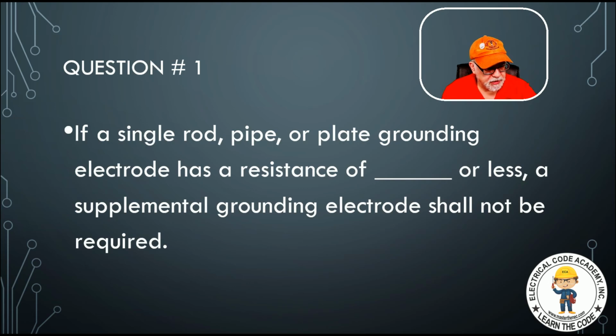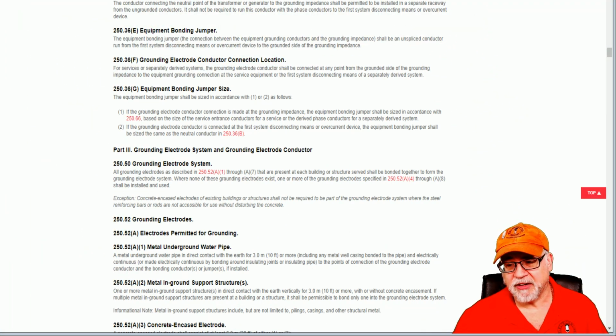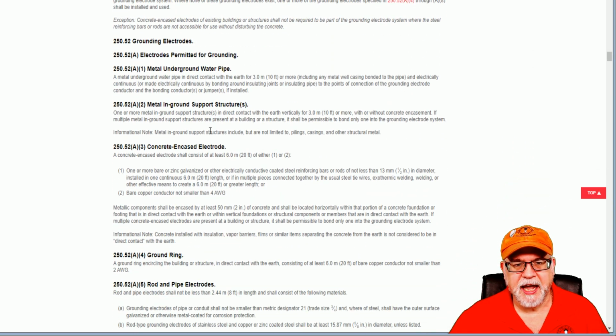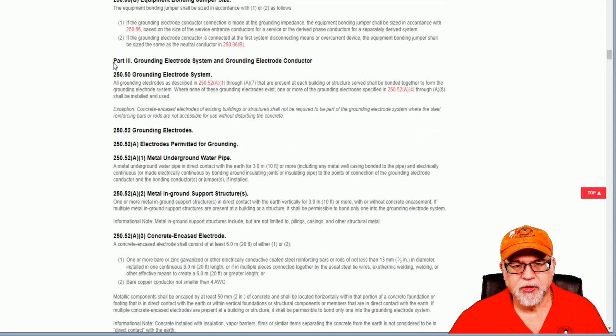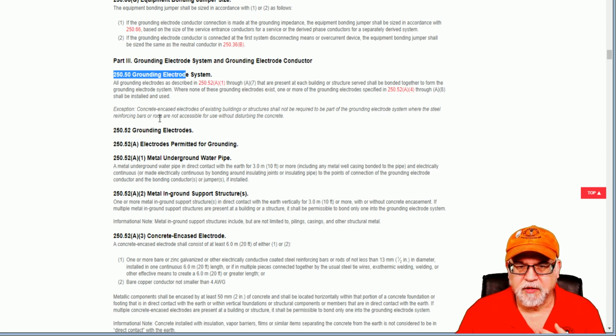Okay, so let's go on and look at the code and get an understanding of where this is coming from. So here's the National Electrical Code. This is the 2020 edition. And first things first, let's look at the rules here. Part 3 is where we're going to be. And you have the general requirement for grounding electrode systems right here in 250.50. That's telling you that the grounding electrodes described in 250.52(A)(1) through (A)(7) that are present at a building or structure served shall be bonded together to form your grounding electrode system.